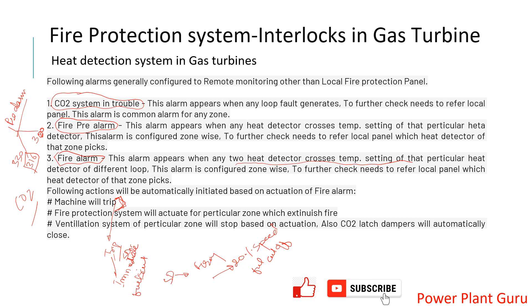After the trip, the CO2 suppression system actuates for the particular zone where the fire alarm is active. Before CO2 is released, all ventilation fans running in that zone will be stopped, and gravity dampers will close once the fans stop. There are also CO2 latch dampers that close when CO2 flows — the CO2 flow pressure initiates the closing of those dampers. These are the actions that occur during a fire alarm and CO2 system actuation.